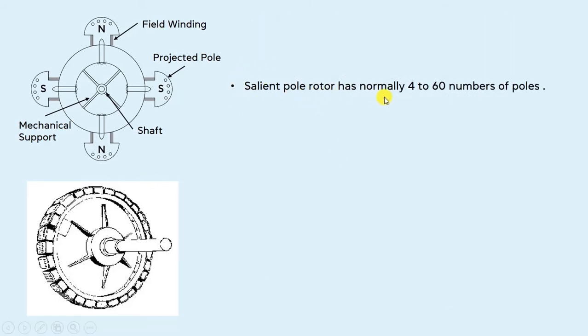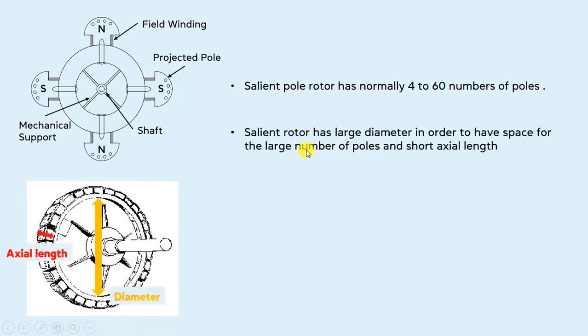Salient type rotor normally has 4 to 60 number of poles, so they have a large number of poles. The salient rotor also has a large diameter in order to have space for the large number of poles, and a short axial length. As you can see in the cross-sectional view of the salient type rotor, it has a large diameter and short axial length.